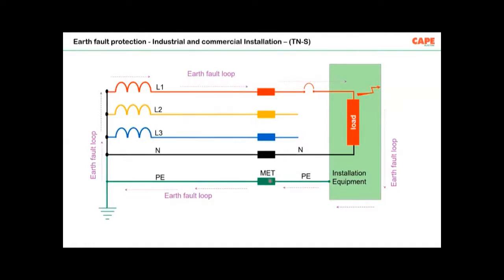Another requirement is that the protective conductor must run very close to the phase conductor, or phase and neutral conductor. The idea is that whenever a fault current flows through the protective conductor, the loop is reduced to a very low level. As a result, the electromagnetic effects or the mechanical force effects are reduced. So basically, in industrial and commercial installations, we are supposed to have a 5-wire system.